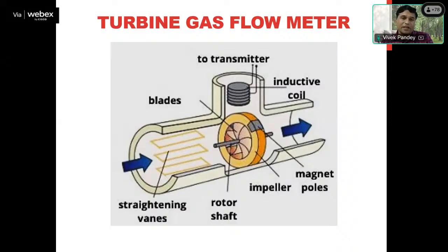You can see in this diagram that inside the gas meter there is an inductive coil, and there is an impeller, which is rotating with the help of a rotating shaft. Within that impeller you can find a small magnetic pole. So what is happening whenever the gas is passing through this pipeline? The direction of the gas should be straight. To make it straight, straightening vanes are there, which provide a straight direction to the gas flow.